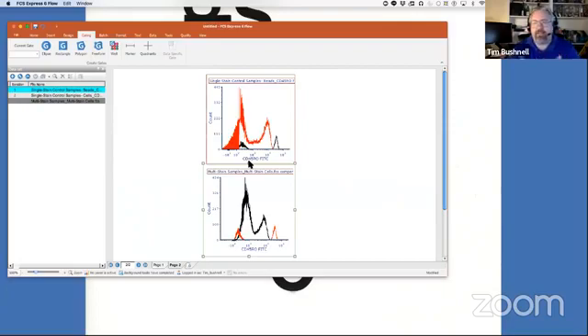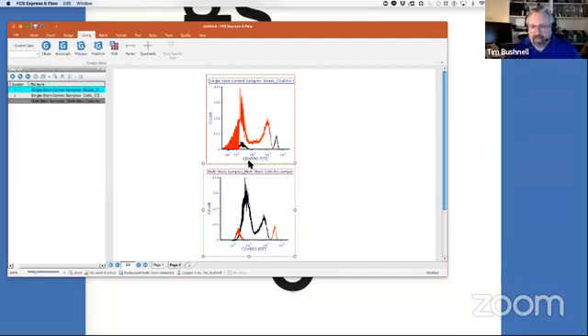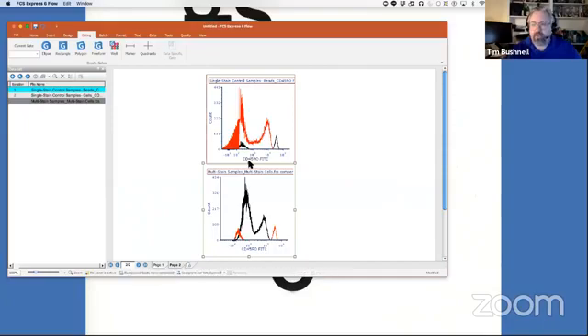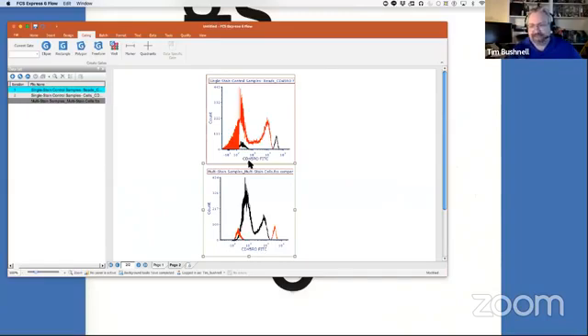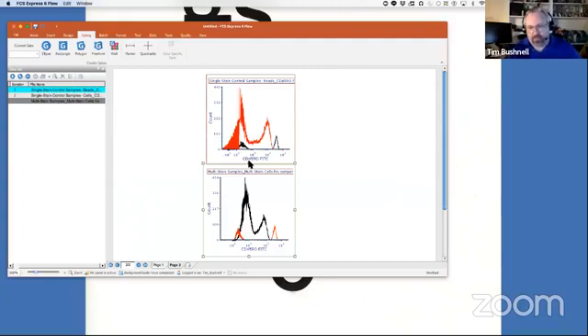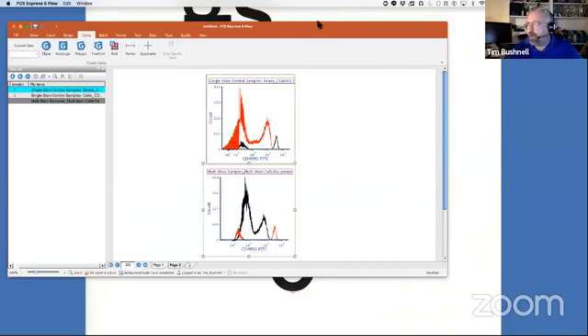And, of course, we've collected everything at the same voltage on our instruments, and this is the same fluorochrome, so we're okay. The biggest issue we would worry about with the fluorochromes would be especially if we're using tandem dyes. The other thing to think about when you're using fluorochromes when you're compensating is that they need to be treated the same way. So if you're doing an intracellular staining, for example, you're doing a fixation permeabilization, your beads or your compensation controls have to be treated the same way. You can't do fresh for your compensation controls and fix for your samples. So you really want to make sure that you're doing both of them correctly and everything is working the same way.